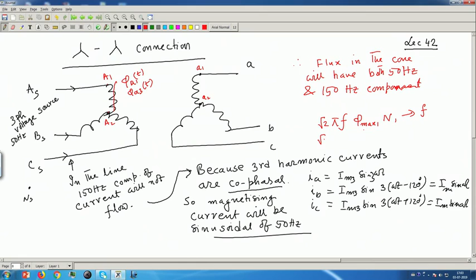Therefore, induced voltage in the coils, say this is A 1, A 2, this is small a 1, small a 2 and so on, B 1, B 2, B 3. So, here these coils will be linked with phi A 1 t fundamental plus phi A 3 t, both of them will be linking this. Therefore, both of them will induce voltage. Induced voltage, mind you, RMS value is equal to root 2 pi f phi max fundamental into N 1 due to fundamental component, and due to third harmonic component the RMS voltage will be root 2 pi 3 f, mind you this factor 3 will come here, phi max of third harmonic component into N 1. Both these voltages will be present. This is of frequency 3 f, that is what I am telling.